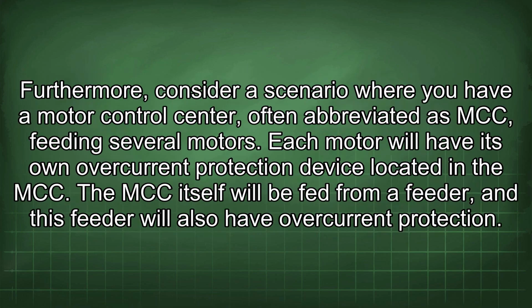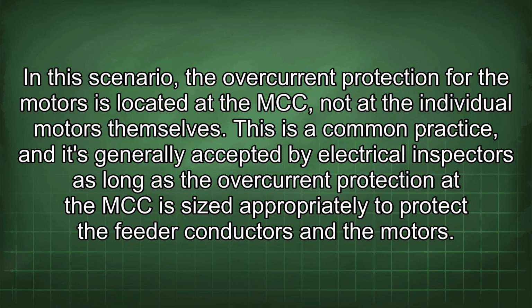Furthermore, consider a scenario where you have a motor control center, often abbreviated as MCC, feeding several motors. Each motor will have its own overcurrent protection device located in the MCC. The MCC itself will be fed from a feeder, and this feeder will also have overcurrent protection. In this scenario, the overcurrent protection for the motors is located at the MCC, not at the individual motors themselves. This is a common practice, and it's generally accepted by electrical inspectors as long as the overcurrent protection at the MCC is sized appropriately to protect the feeder conductors and the motors.